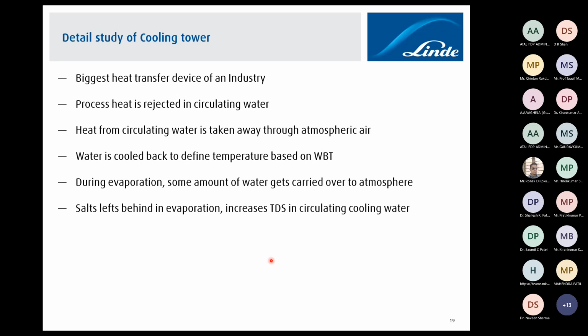In any evaporation process, what happens? Only pure vapor is liberated. You will find all the salt or residual part always remains inside the system, and whatever vapor is evaporated is always pure. So over a period of time you can see that total dissolved solid concentration starts accumulating in the cooling water. That's why we need to blow down and remove some impurities so that we are always able to maintain our desired TDS in the circulating water.